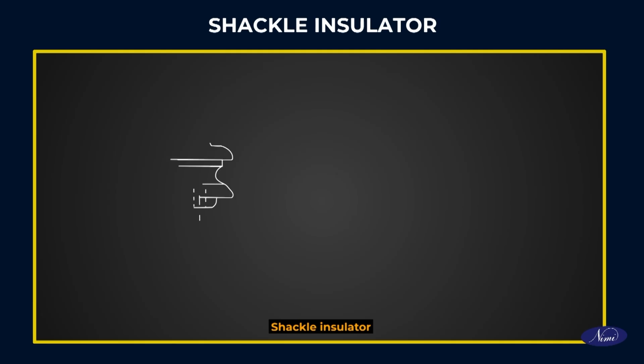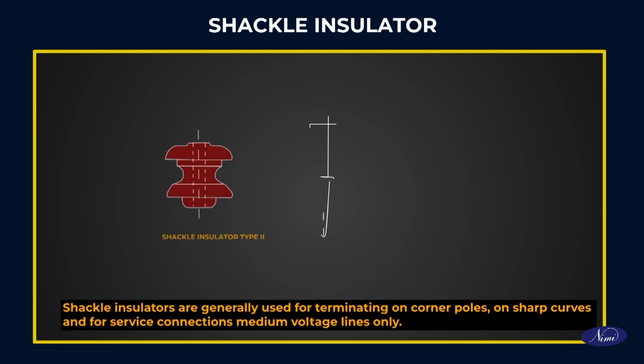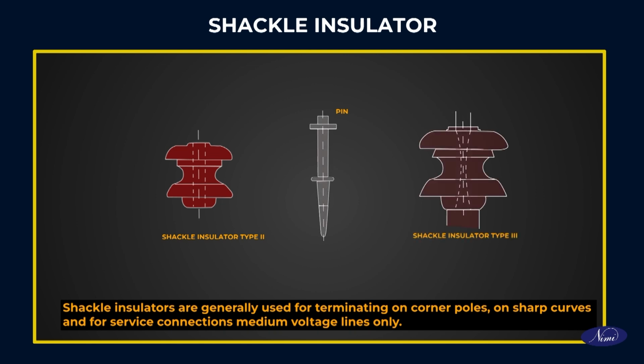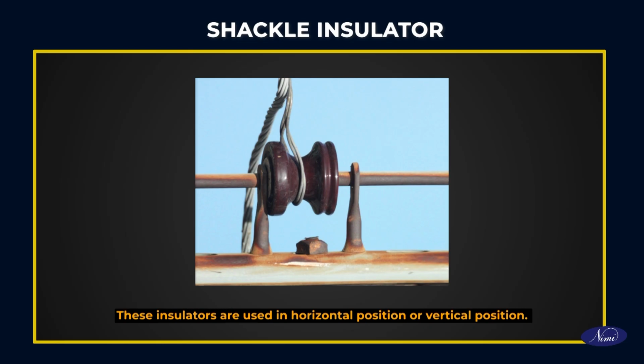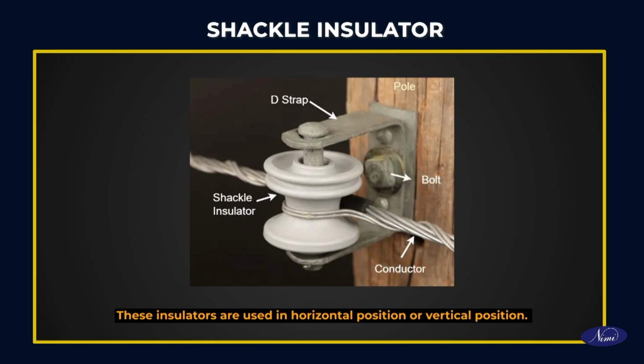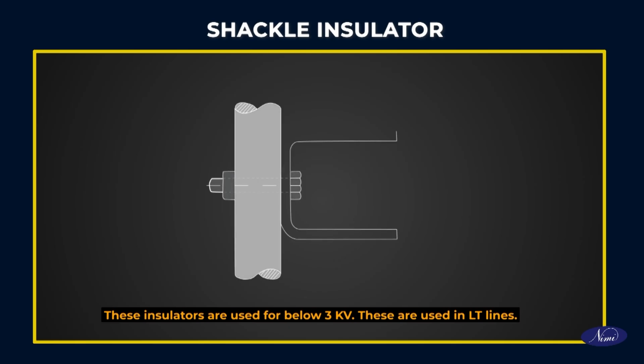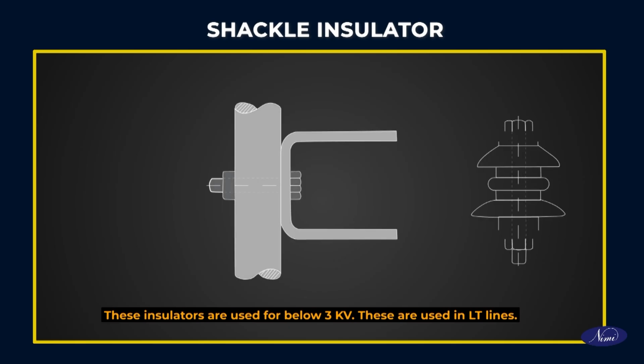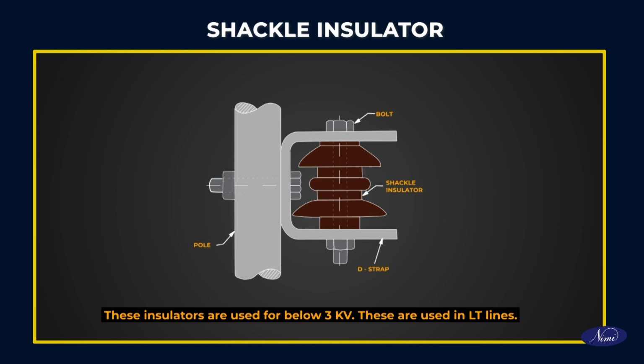Shackle insulator. Shackle insulators are generally used for terminating on corner poles, on sharp curves, and for service connections on medium voltage lines only. These insulators are used in horizontal position or vertical position. These insulators are used for below 3 kV. These are used in LT lines.